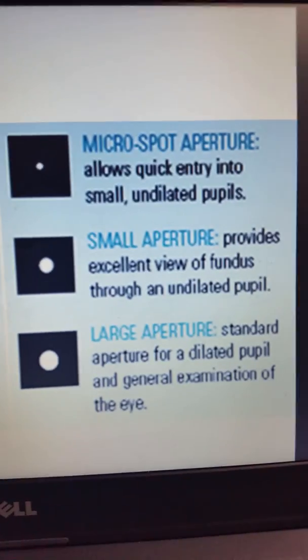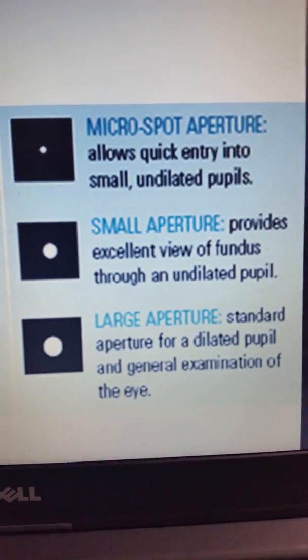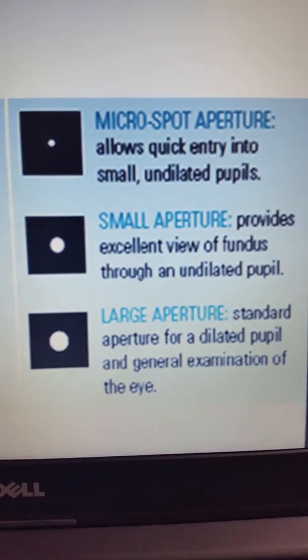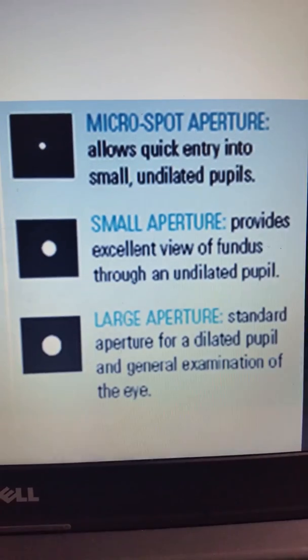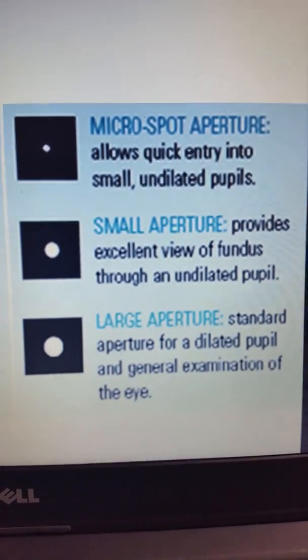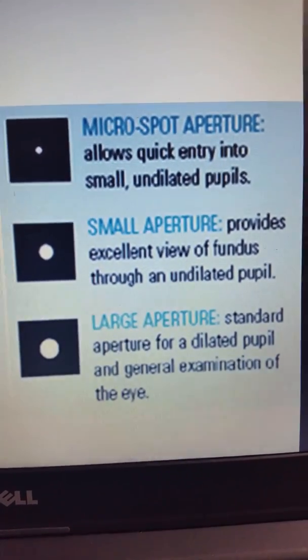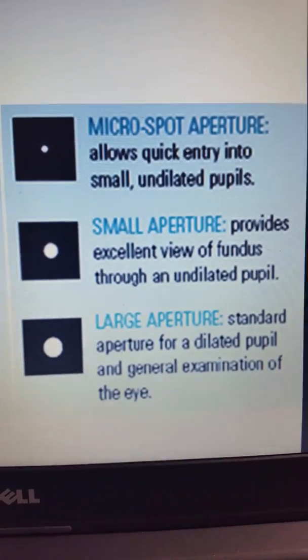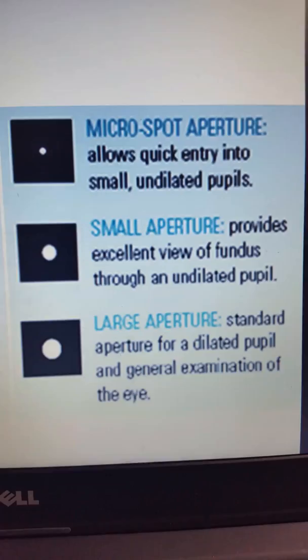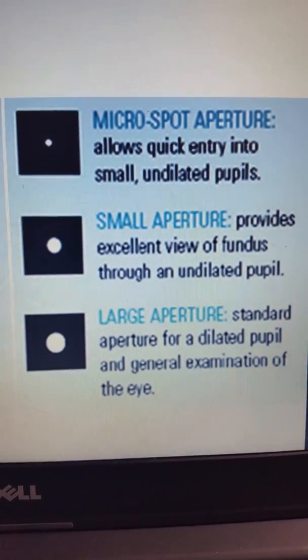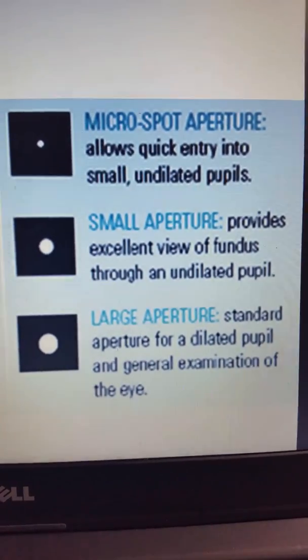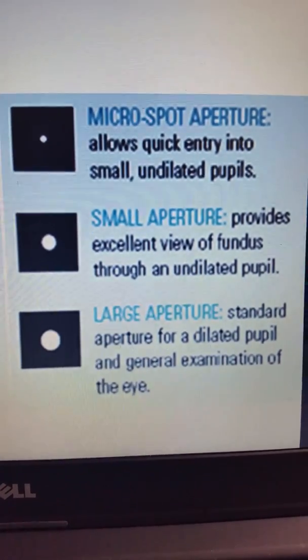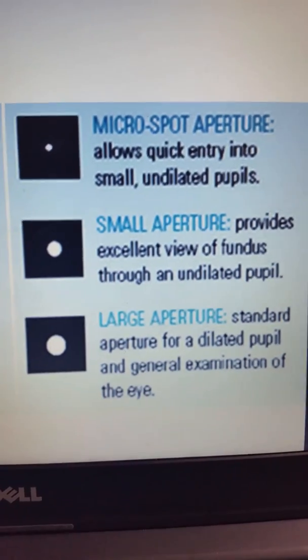The size of the aperture relates to the pupil condition: your micro spot aperture is for small undilated pupils, your small aperture is used on the majority of undilated eyes, and your large aperture is the standard for dilated pupils.